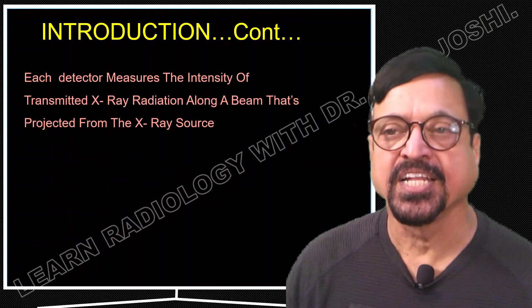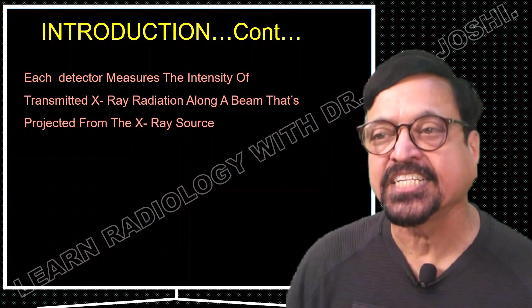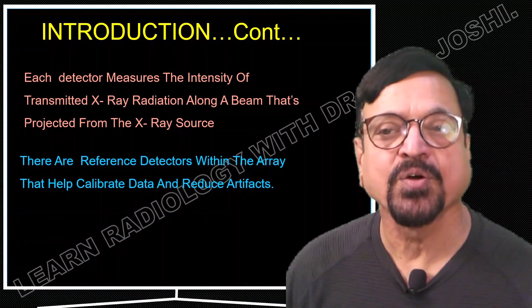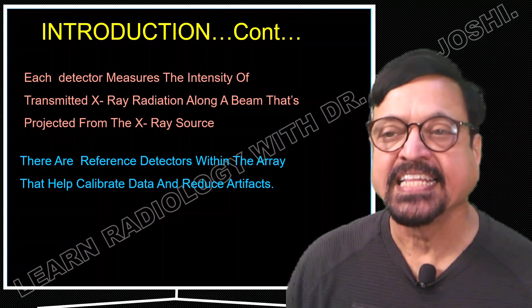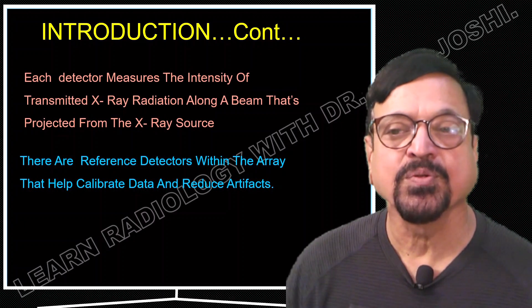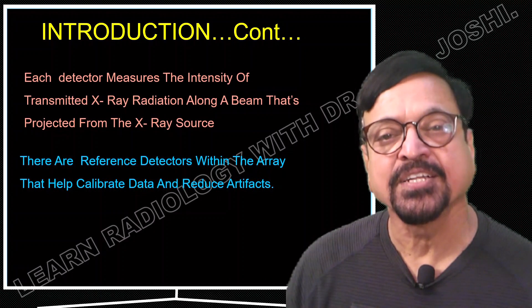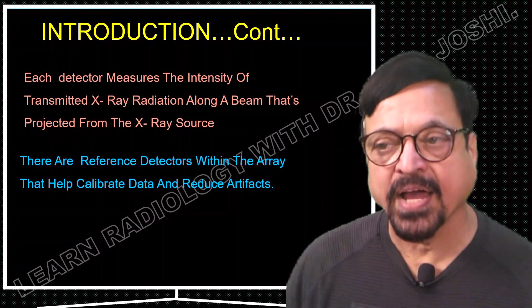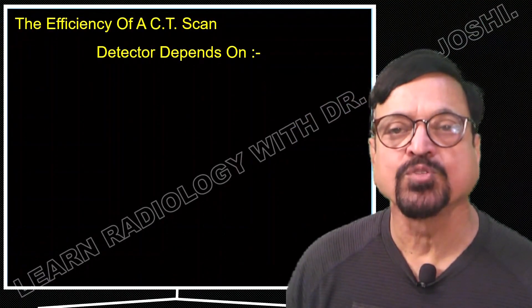Each detector measures the intensity of the transmitted X-ray radiation along the beam projected from the X-ray source. In addition to the main detectors, there are also reference detectors within the array. They are positioned next to the routine detectors and serve two roles: they help calibrate the data and they reduce artifacts — both important contributions to image quality.